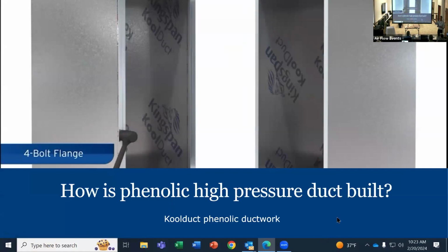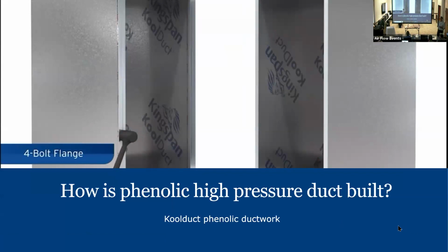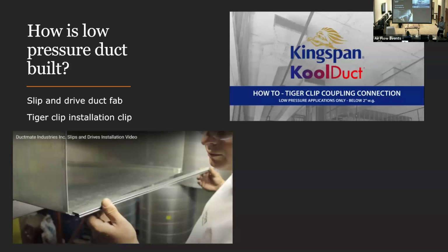So that high pressure seal class A duct is leakage class 4. This is leakage class 3. So it's as good as, it's a little bit better. All right, now that's high pressure side. Everything looks the same. Here's the low pressure side. We're gonna play that lower left Ductmate Industries video.